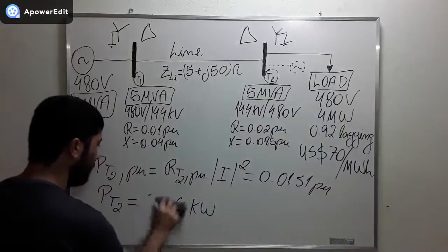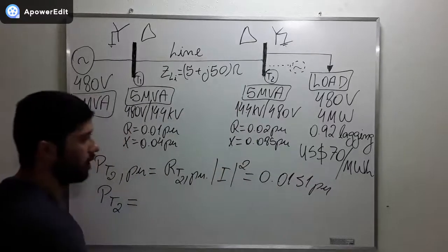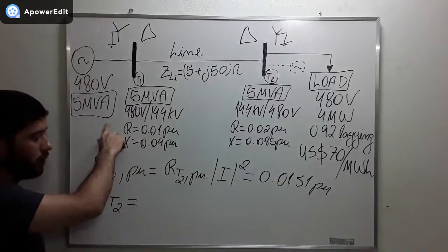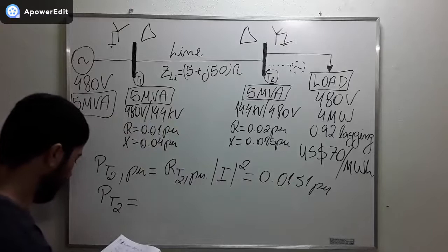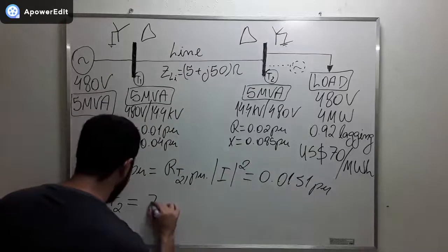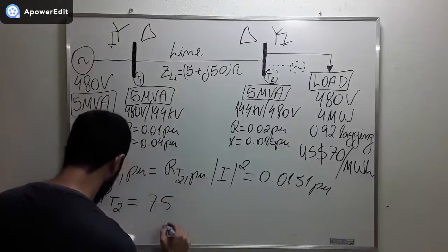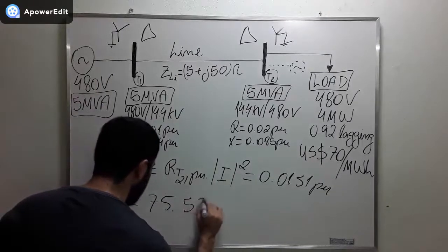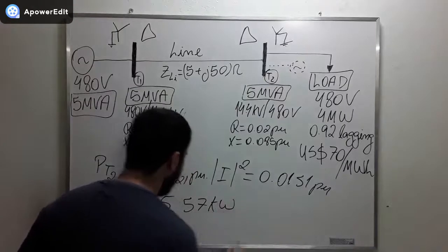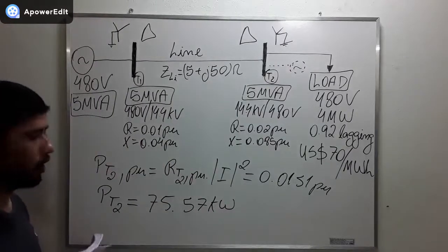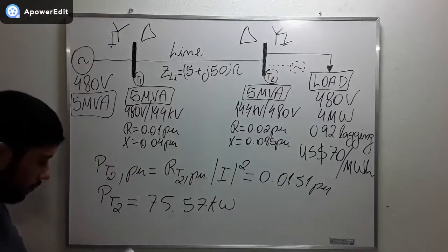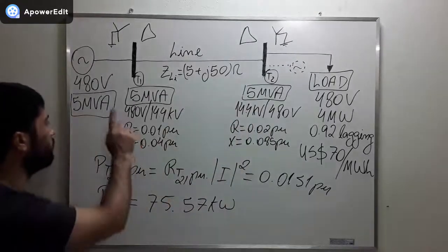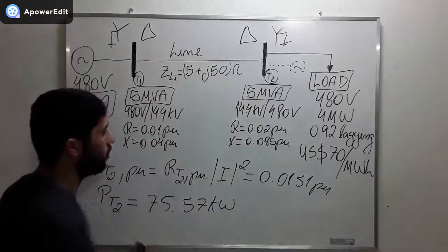And here we multiply this in per unit by this base value, and we find the real power lost in transformer number 2, which is 75.57 kilowatts.